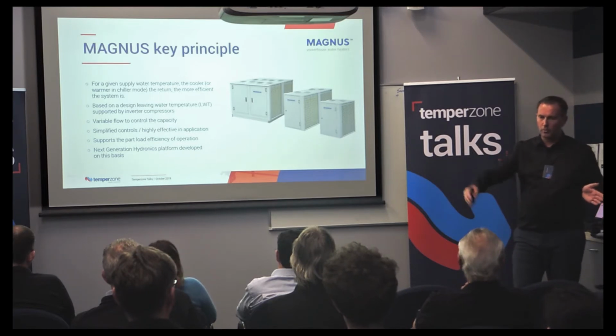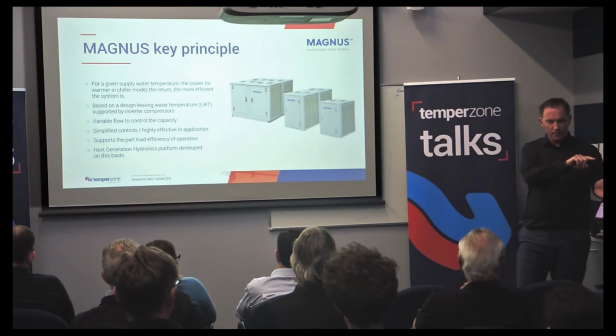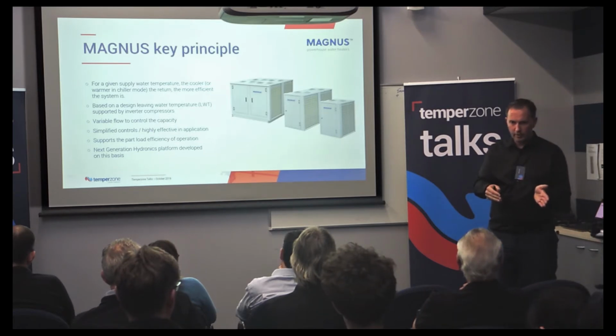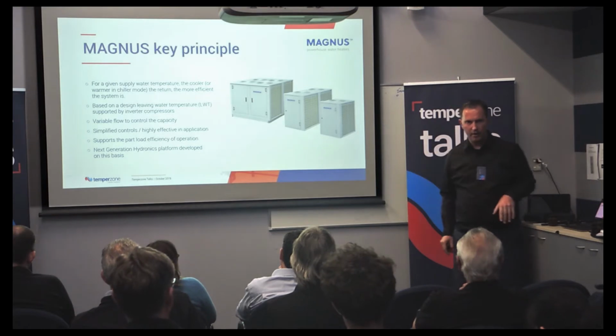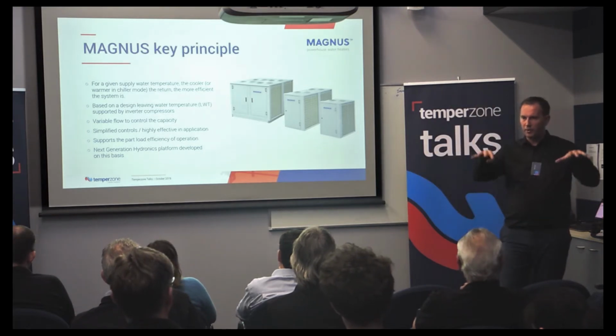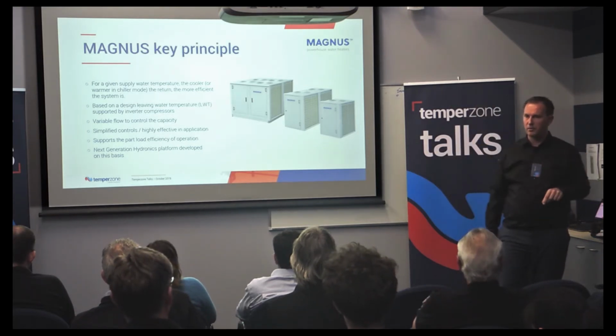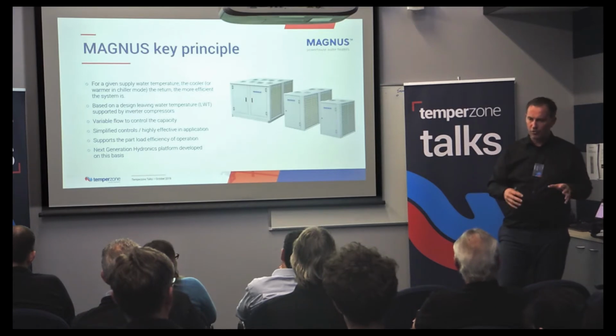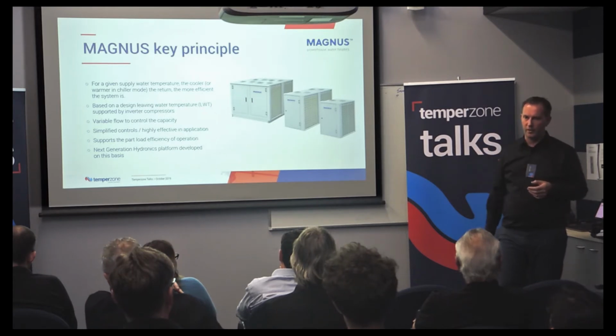Where we've got multiple inverters, once we move out of the peak efficiency point of each inverter, we switch on another one and another one and another until we have them all going, and then we ramp them all up and do it simultaneously. And then as the load drops, we drop them off so that we are always keeping within the peak performance for each inverter.